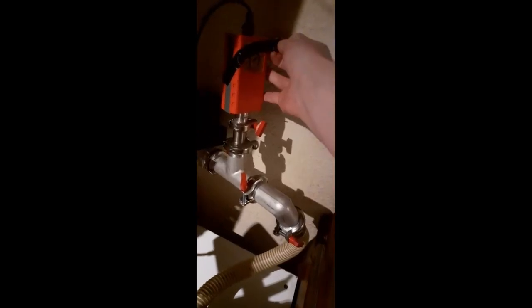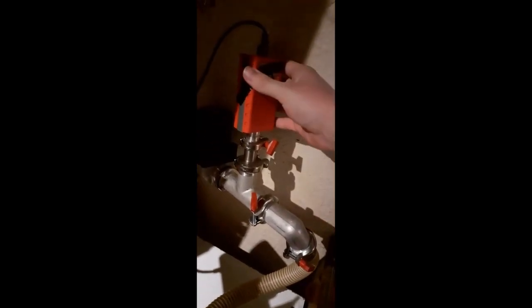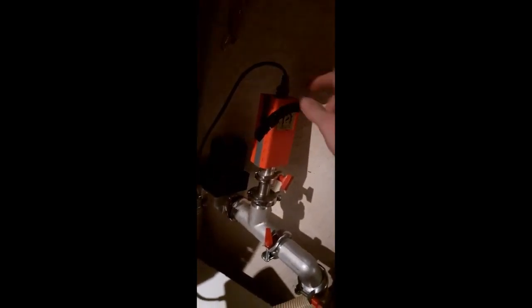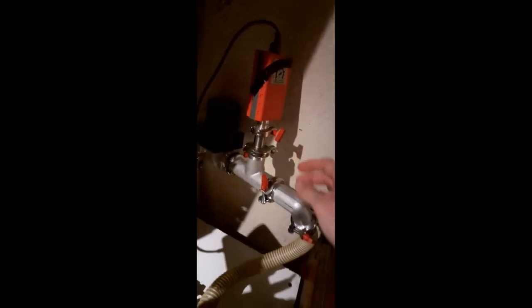Then we have a vacuum gauge here. This is an Edwards APG active Pirani gauge, and this is just a complete unit. You just give it 24 volts and it gives you a 0 to 10 volt output, so it's very easy to interface. And some more flanges here, some more hose here. I've decoupled these two, I'll tell you why later. And this then feeds into the turbo pump.